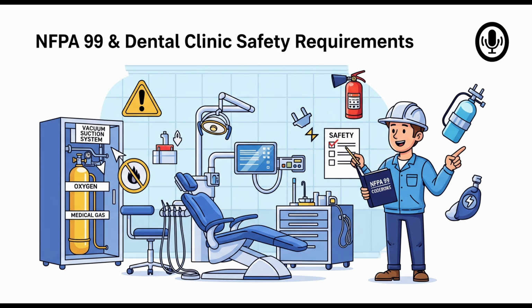But you still need all those components, right? Compressor, dryer, filters. No, absolutely. You still need the full sequence to ensure the air quality meets the medical air standards: dry, clean, free of contaminants. That part doesn't change. It's just the redundancy requirement that's relaxed for Category 3 air sources. What about the vacuum pumps? Same simplex allowance.